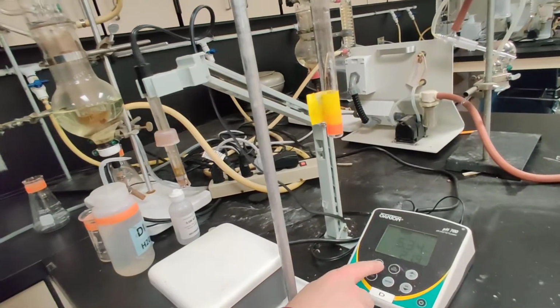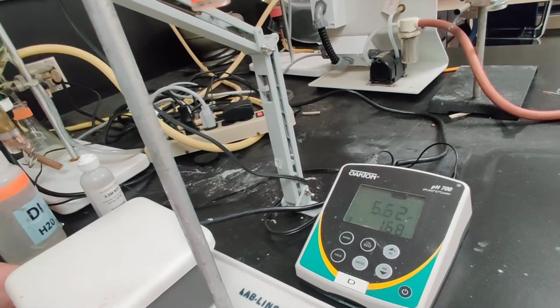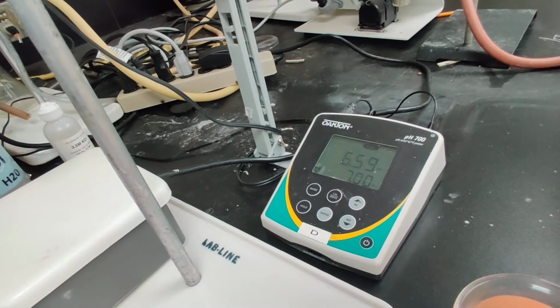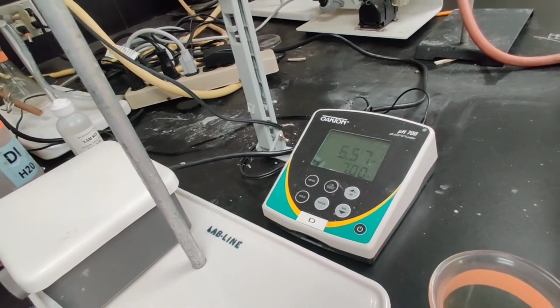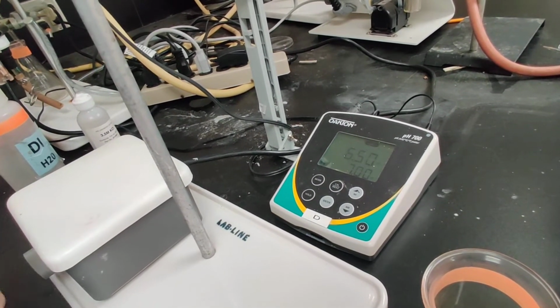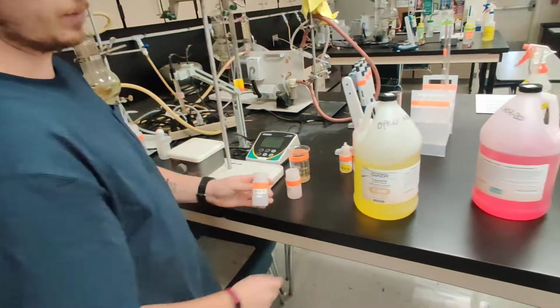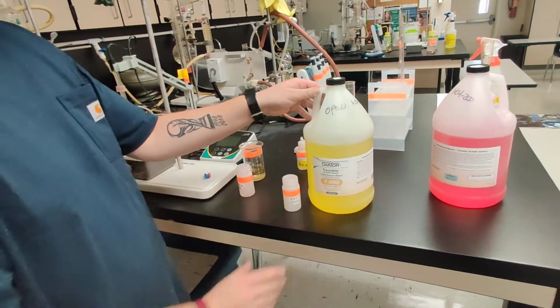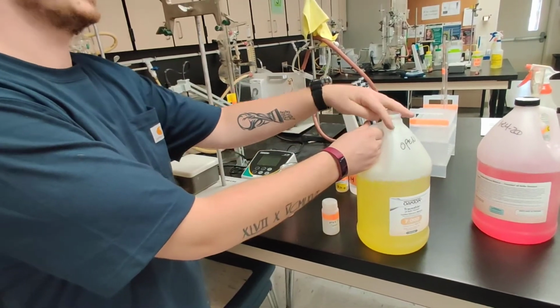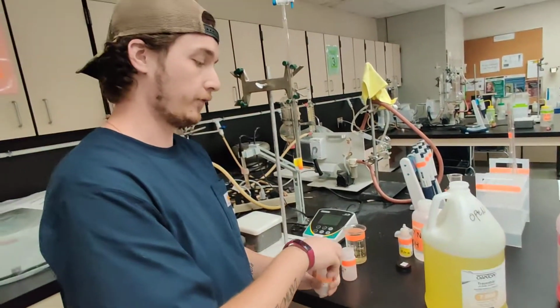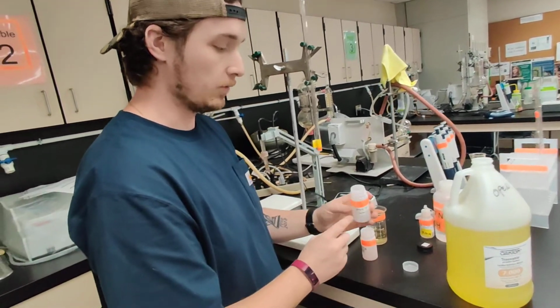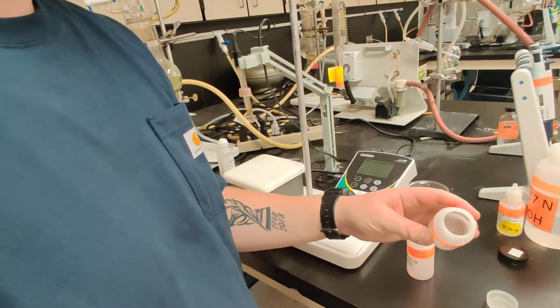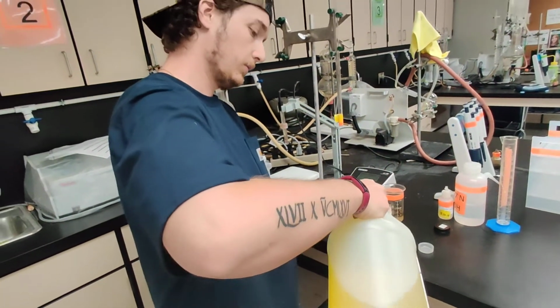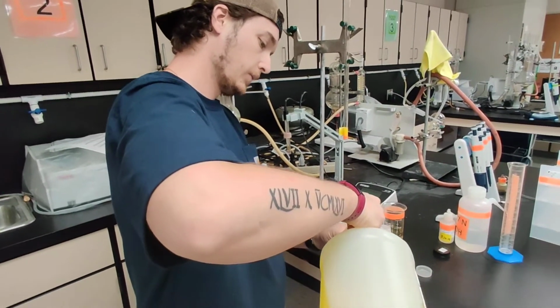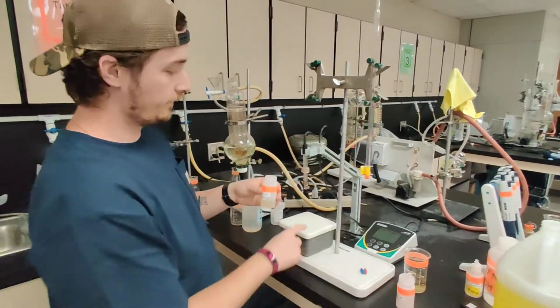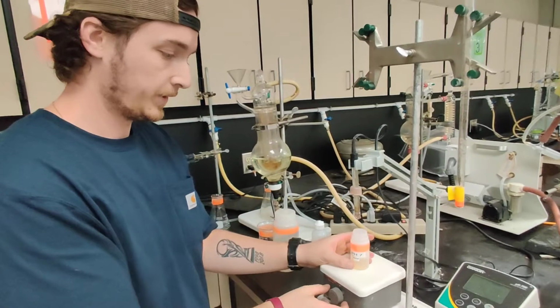So for this one, what we'll do is hit cal, and it'll ask first for either pH 4 or 7. For this one, it is asking for pH 7. So what we'll use here is a buffer solution, and note that those tend to lose strength with time, so you always want to use a fresh solution. In this little bottle, you'll want to make sure there's a stir bar and some solution in there. You don't need very much, just enough for the probe to be fully submerged in the buffer.